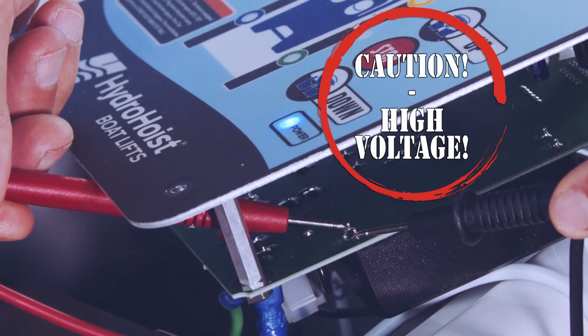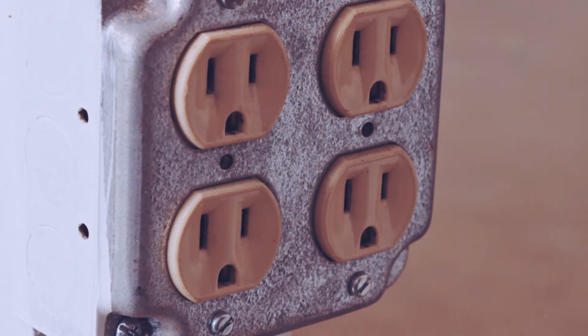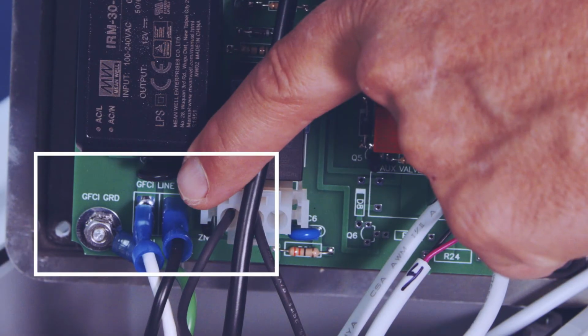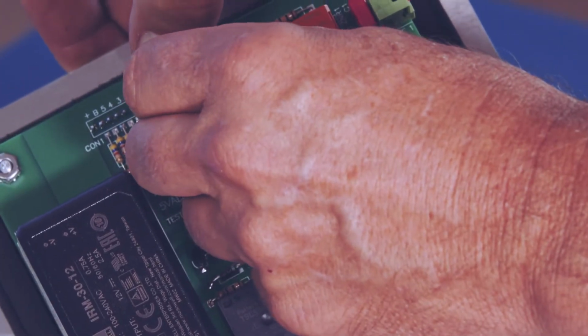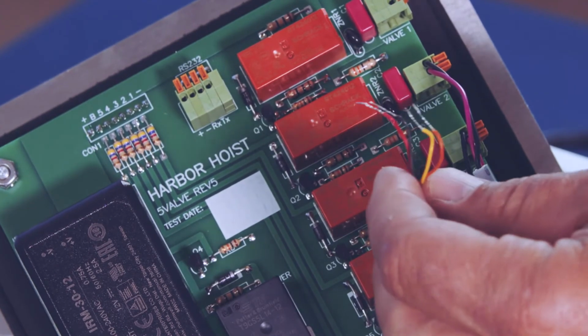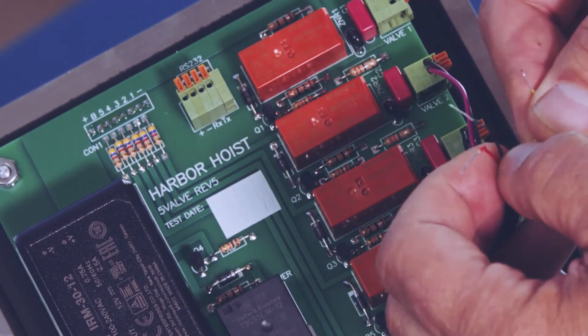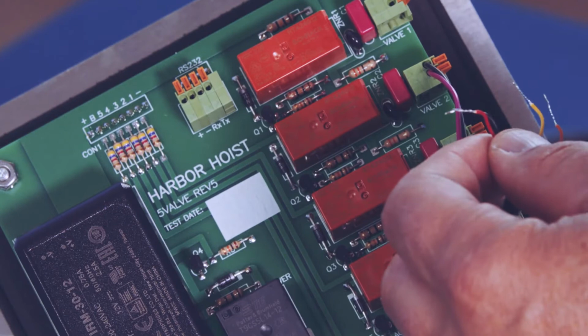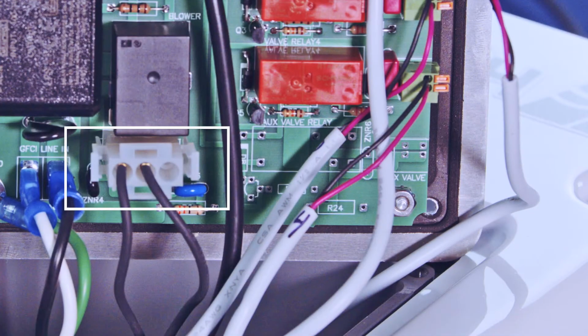Caution, high voltage. With power removed from the control, remove spade connections for power lines and remove the nut holding the ground connection. Remove wire leads for the level sensor and valves by pushing down on the orange lever on the connector. Make note of the colors of wires and where they are in the connector for reassembly. Remove white blower power connector by squeezing both sides of it and pulling up.